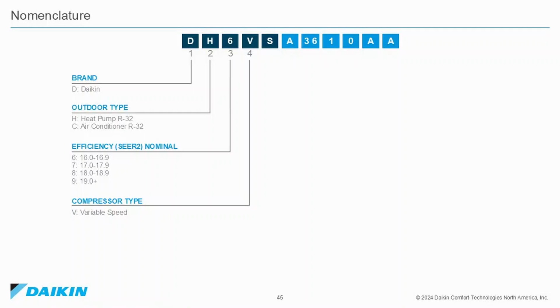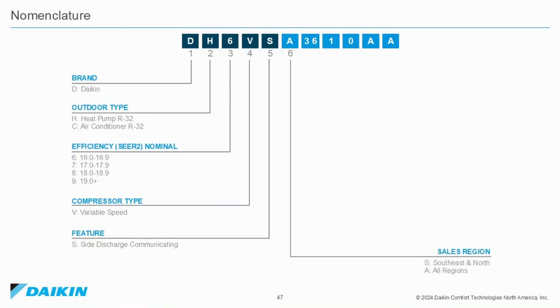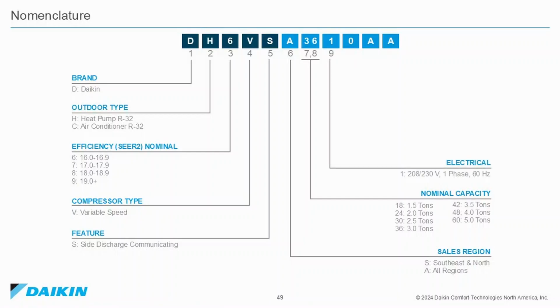V is for a variable speed inverter drive compressor. The next position is the feature. S for side discharge communicating system. The next position is for the sales region. A is all regions. S would be the southeast and north. The next position, 36, stands for the nominal capacity. 18, 24, 30, 36, 42, 48, or 60,000 BTUs. The next position is electrical input. This unit is 208-230 single phase 60 cycle.